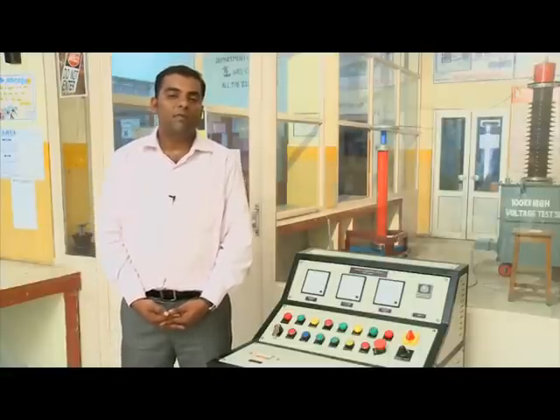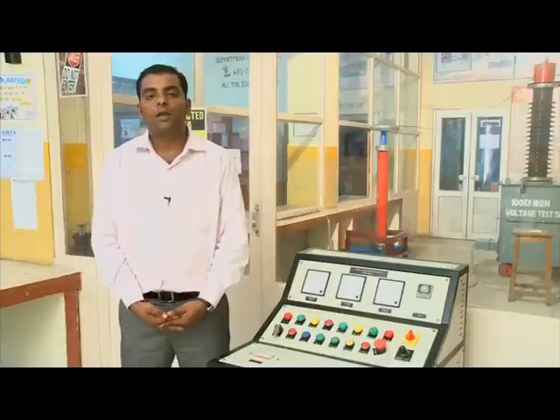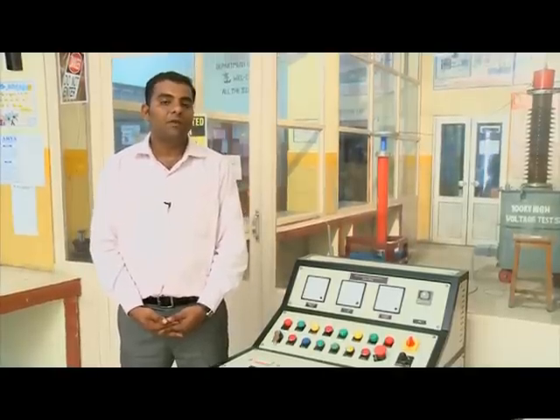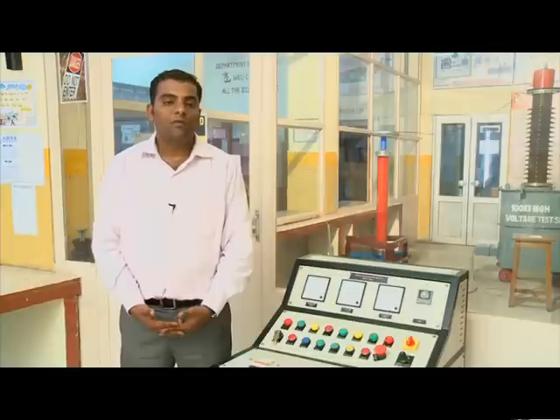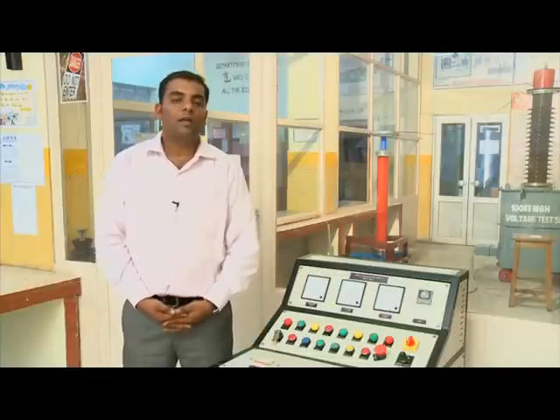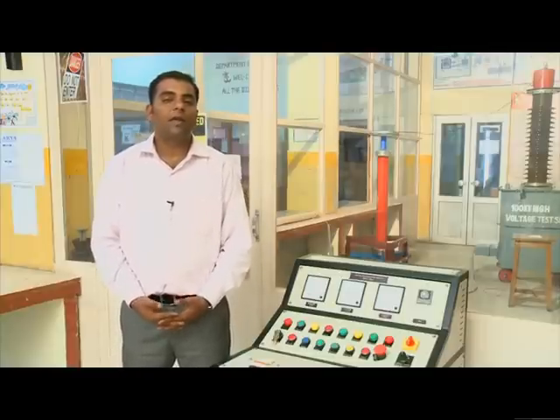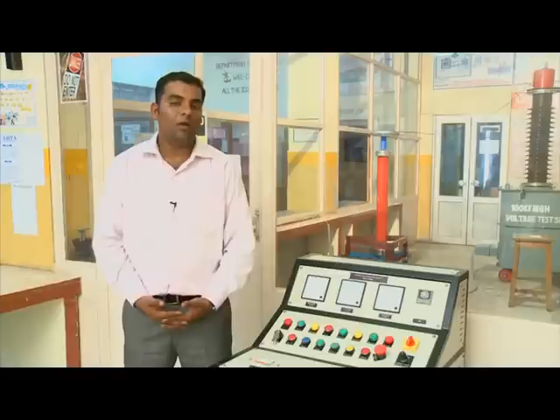With the help of the high voltage testing setup, we have analyzed the peak value of the transmitted voltage and the peak value of the voltage on which corona loss will occur. With this setup, we also found out the efficiency of the insulator string. We have found out the value of that voltage on which the breakdown of air will occur, for suitable and most efficient transmission of high voltage.